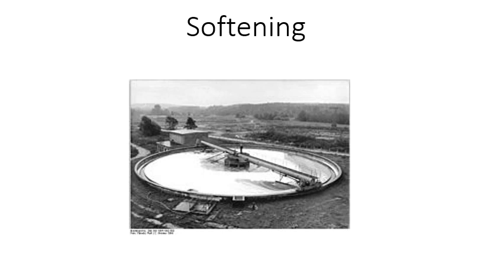Step 9 is the removal of all lime from the system. Waste sludge comes out the bottom of the clarifier. Periodic or automatic manual wasting occurs based on lime level or time. Wasted lime goes to a lagoon or disposal system.